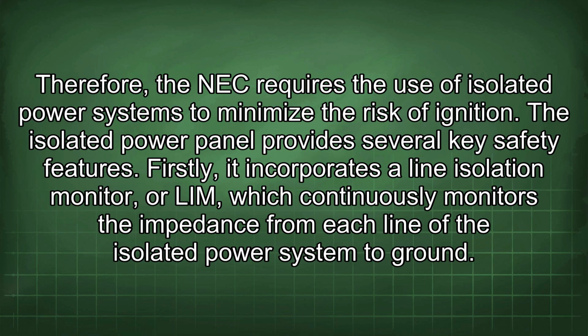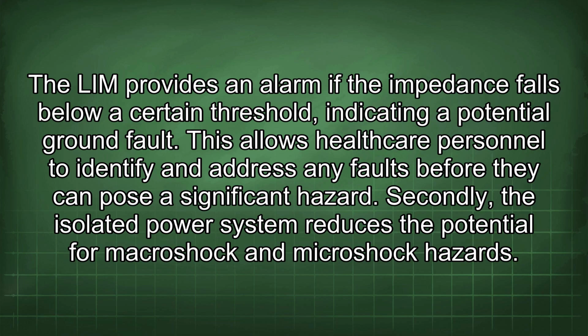The isolated power panel provides several key safety features. Firstly, it incorporates a line isolation monitor, or LIM, which continuously monitors the impedance from each line of the isolated power system to ground. The LIM provides an alarm if the impedance falls below a certain threshold, indicating a potential ground fault. This allows healthcare personnel to identify and address any faults before they can pose a significant hazard.